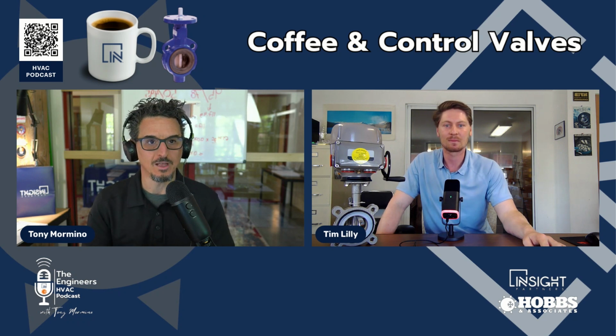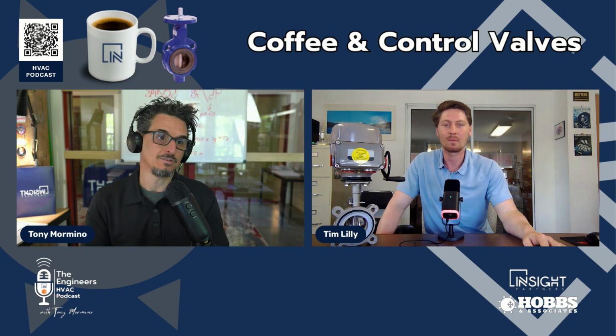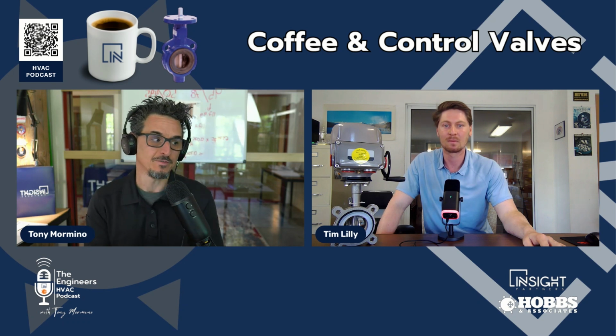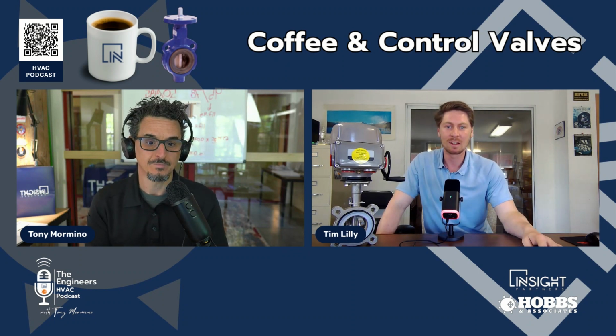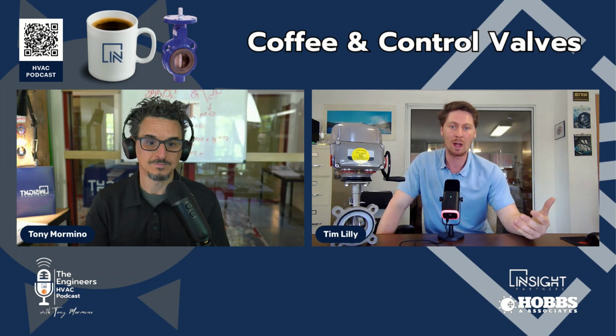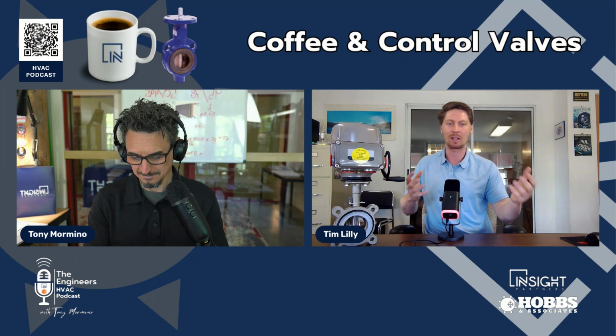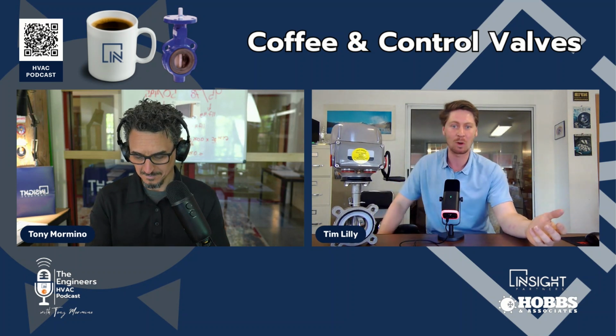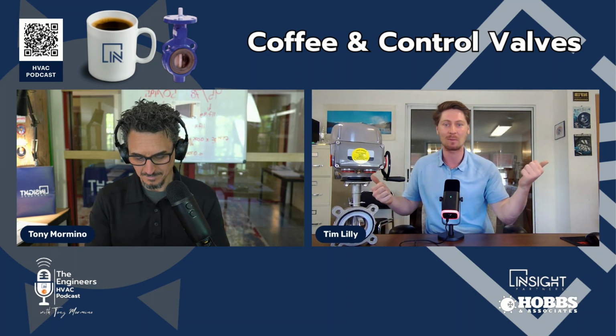So, but you're saying like in the industrial world, it's way more critical. The valve is treated like we would maybe treat a chiller. In HVAC, it's not. It's kind of an afterthought, but is equally as important, right? If your valve's not controlling right, if it's not the right type of valve, and you don't get the right flow into the coil, it doesn't matter what kind of chiller you have, right? Exactly. And we've come a long way with the chiller technology, and they can handle some variance. But in the HVAC world, one side of the building might be facing the sun, the other side might be in the shade.